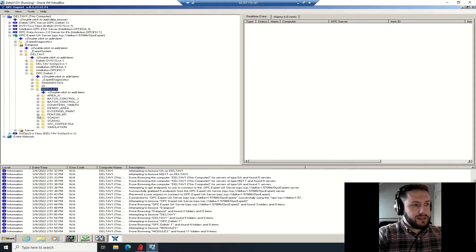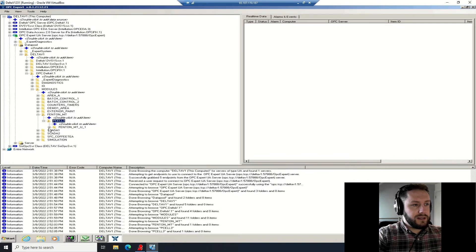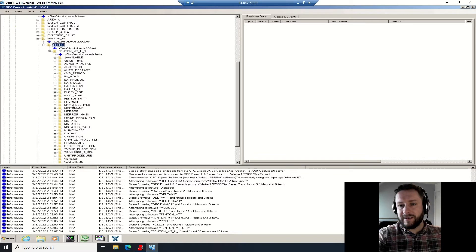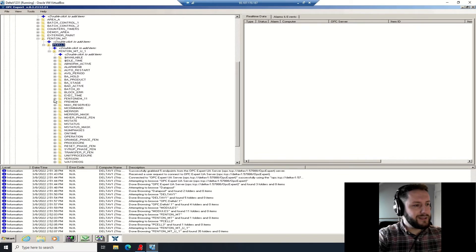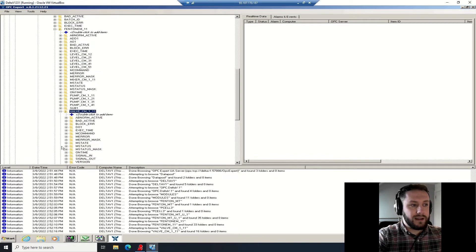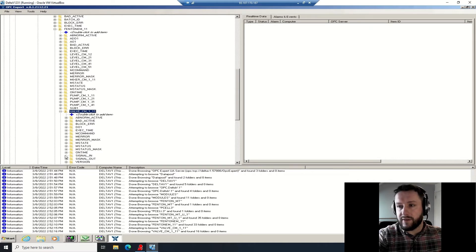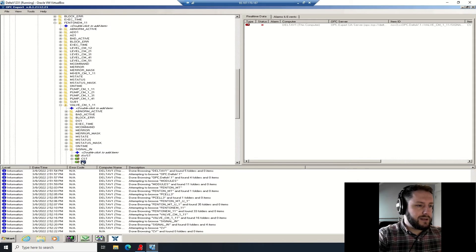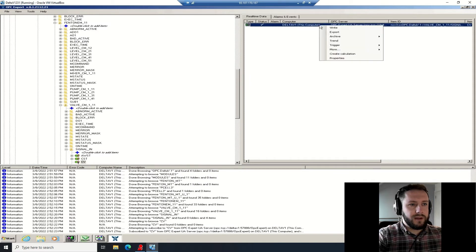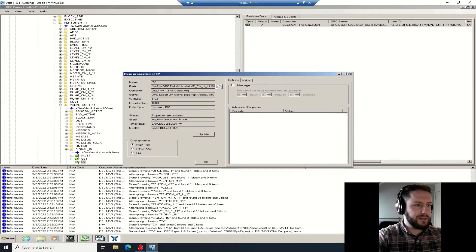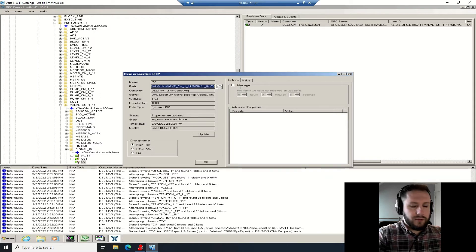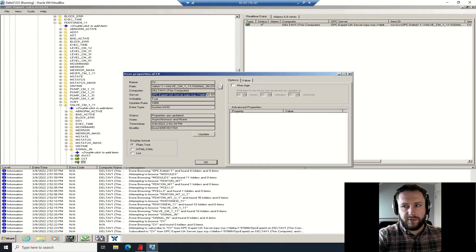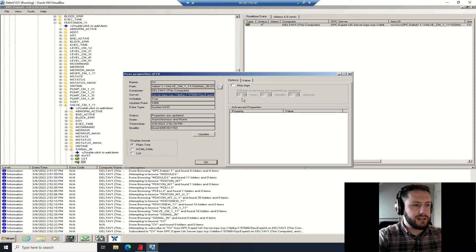Through the process cell into the unit model, into the communications - or pardon me, the control modules - and then down into the signals. So I'm looking for a level CM, and then signal in. Signal in and CV, which stands for current value. You will see these tags appear as green. I want you to double click that and it will open up on the right hand side. You right click this and select properties, and this will give us two major pieces of information. We'll get the path, which we'll need to reference the tag, and you will get the server address.